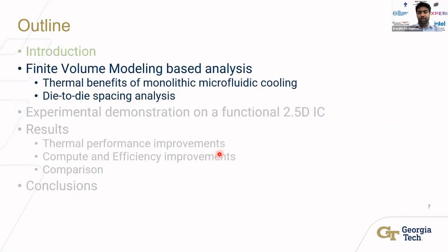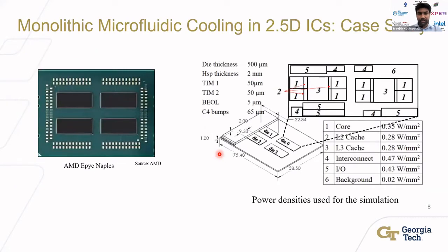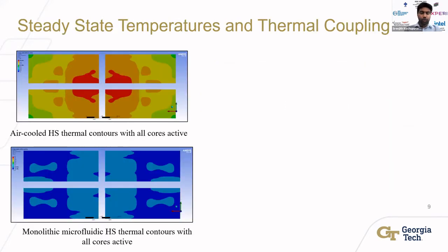To understand how this works in a practical system, we performed finite volume-based modeling analysis. We chose an older-generation AMD EPYC Naples processor as the test case, using publicly available data for power densities of each core complex die, and the dimensions of the package and dice. This configuration reached close to 200 watts of total package power dissipation, which we compared across multiple cooling solutions.